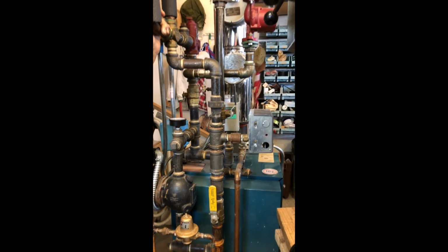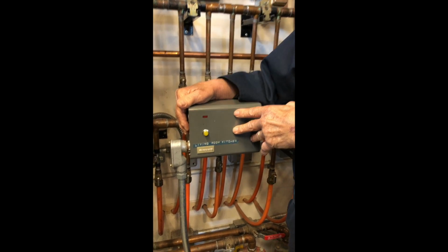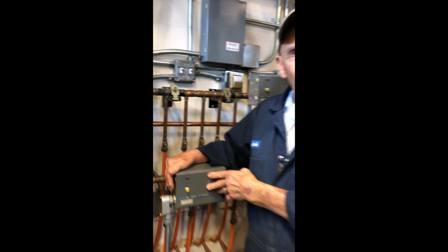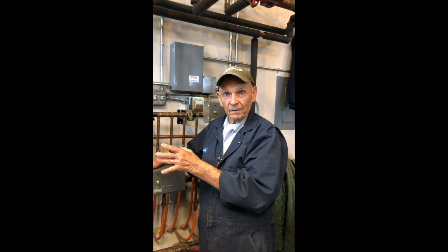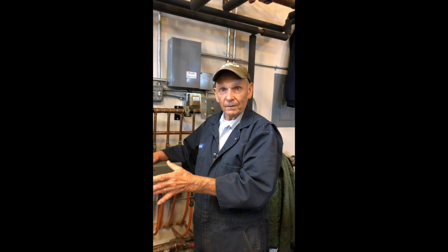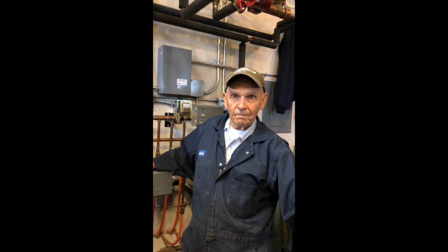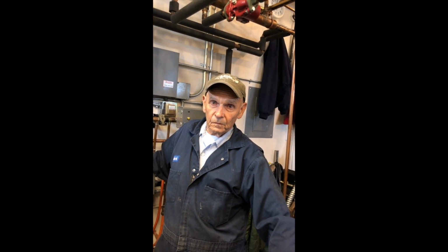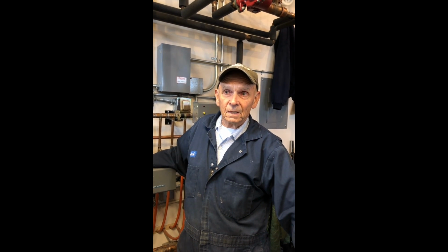It could be only one zone calling for heat. And this control here on each zone starts the pump and starts the boiler for one zone. Should all of them call for heat, then they all work together and open up and start the pumps, and you heat the whole system. But as long as you have the wood boiler going and you keep it stoked, then the oil boiler really never kicks on. Yes, correct. And that happens when the wood boiler reaches 120 degrees.